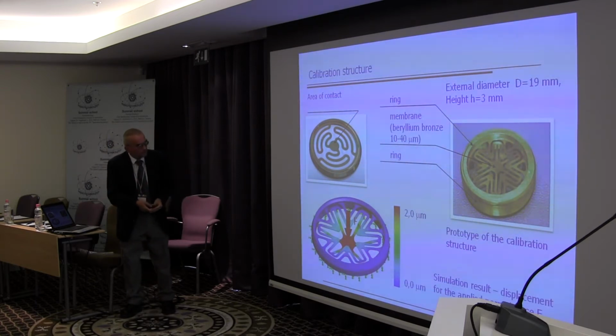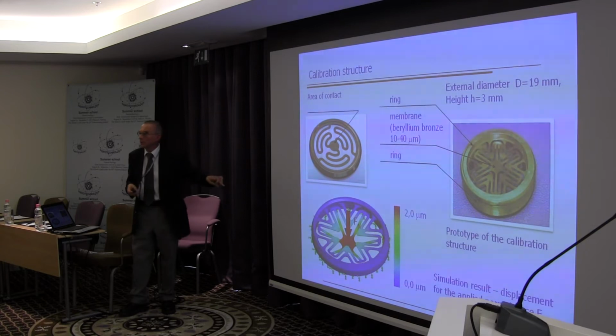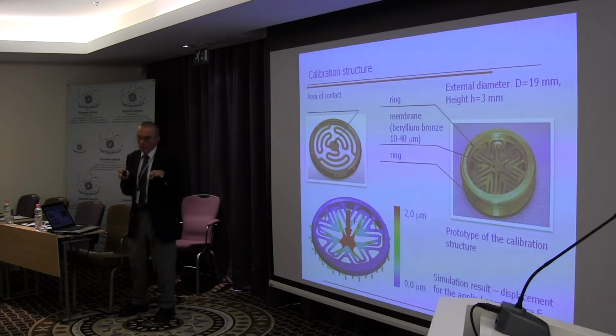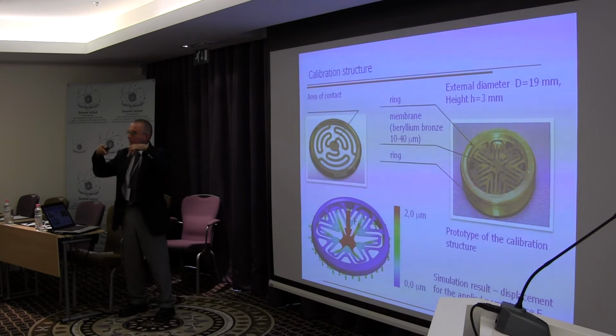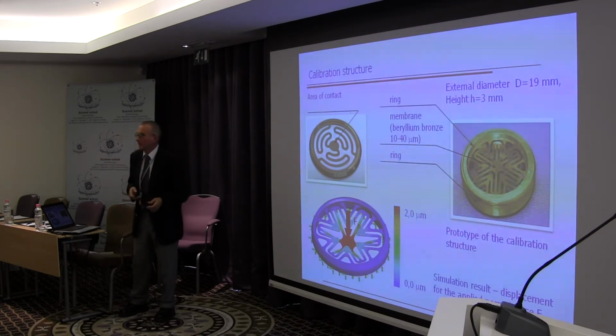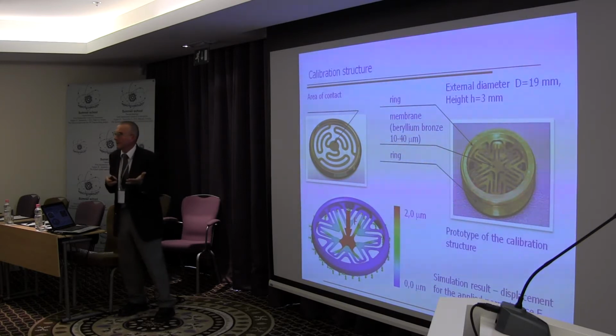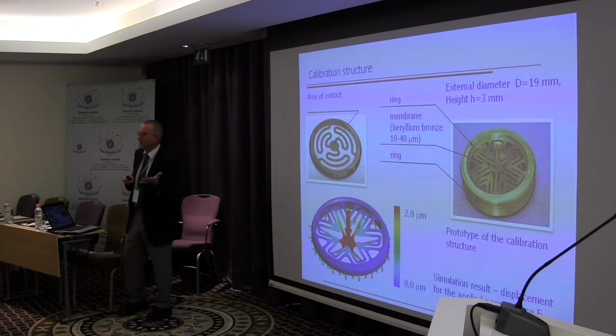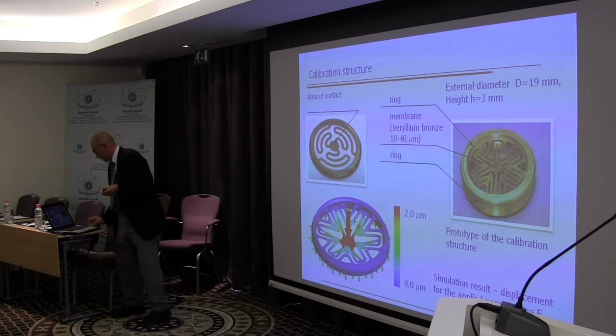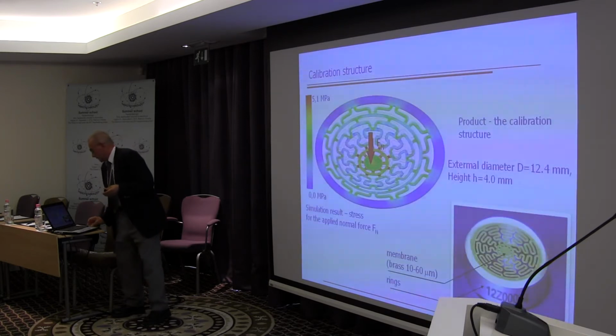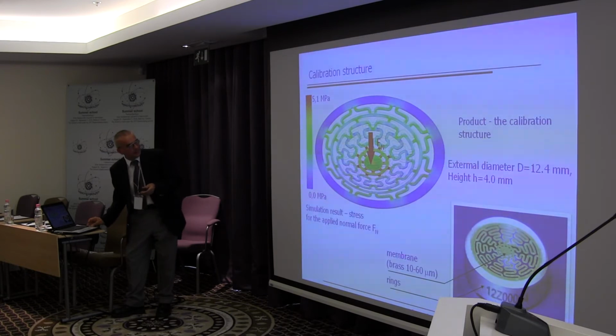Of course, what is important is to look at how the system behaves during calibration when the tip is not contacting exactly in the center. And these structures were optimized in this sense. So there is some tolerance area, so that the tip need not be exactly in the center during calibration. And the finite element method was used, modeling, and so on. So it was optimized in this way. You can see the results here, something like this.